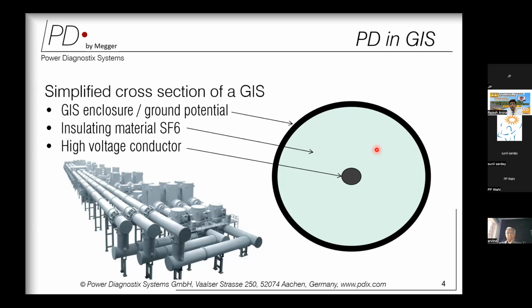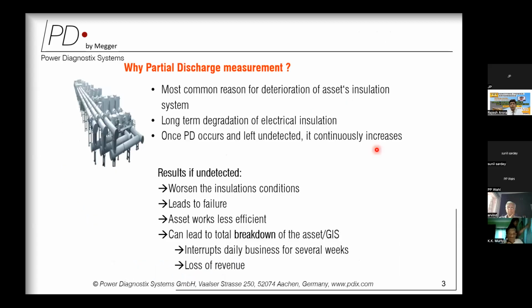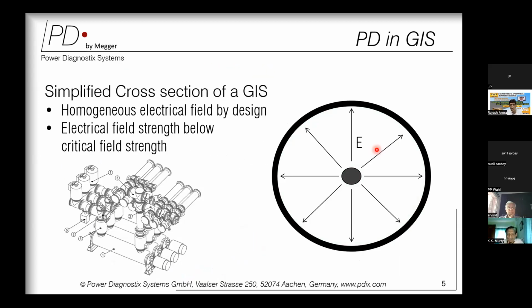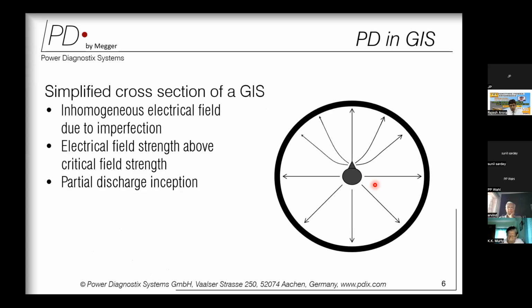Now, in general condition, this insulating material is designed in such a way that by design it gives a homogeneous electric field. The electric field across the GIS is quite homogeneous, and the strength of this electric field is just below the critical field strength, and hence everything is functioning smoothly. In case of a certain imperfection, as we see here on the central conductor, the electric field strength at that particular point increases above the critical field strength, and that is where the inception of partial discharge happens, which could be associated with some sparking mechanism inside the GIS.